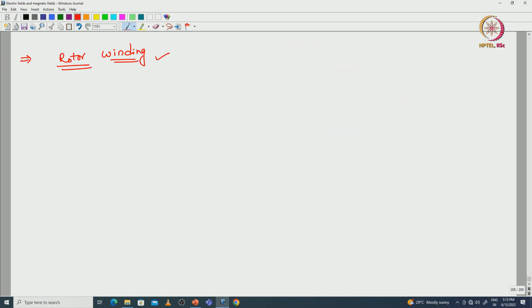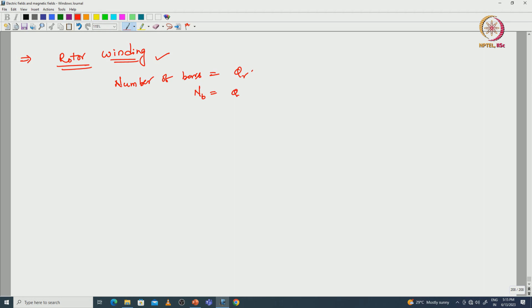We will start with the rotor winding. First, we will find the number of bars. The number of bars is equal to the number of rotor slots: NB equals QR. Then we will calculate the bar current.